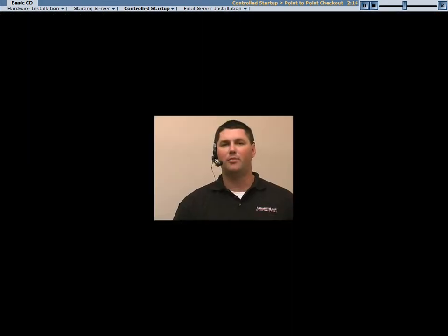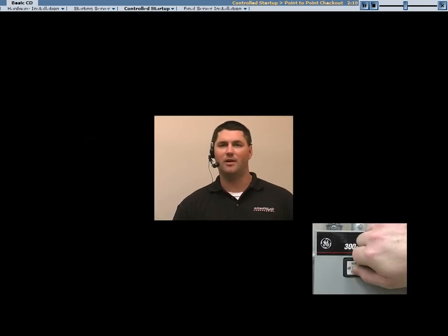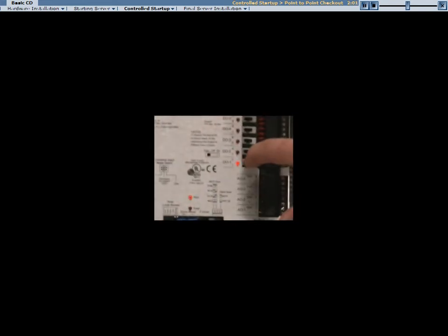For the binary outputs, on the equipment starter, place the equipment's HOA switch in the automatic position. Next, on the control module, set the binary output's HOA switch to on. Verify that the BO light has turned on. Be aware that when you turn the BO on, you are sending a signal to the equipment and it will respond accordingly, in this case by turning on. Take any necessary precautions to prevent equipment damage.